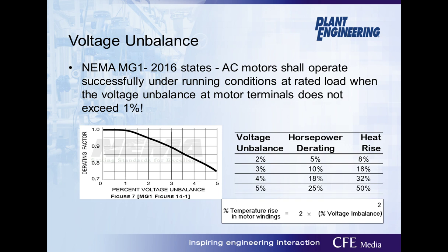So continuing to look at voltage, we talked about over voltage and under voltage. Another issue is voltage imbalance. I've completed a couple of metering and verification projects in my time where we have definitely witnessed voltage imbalance in many different plant settings and varying levels of voltage imbalance.